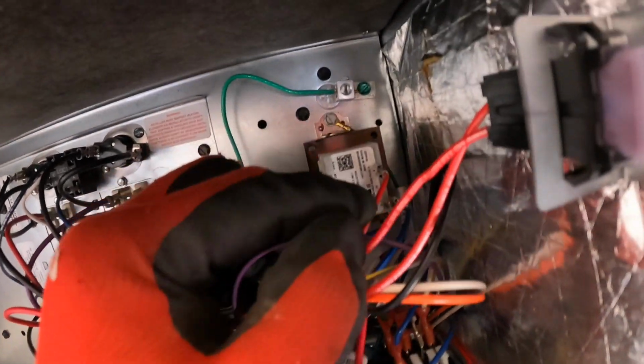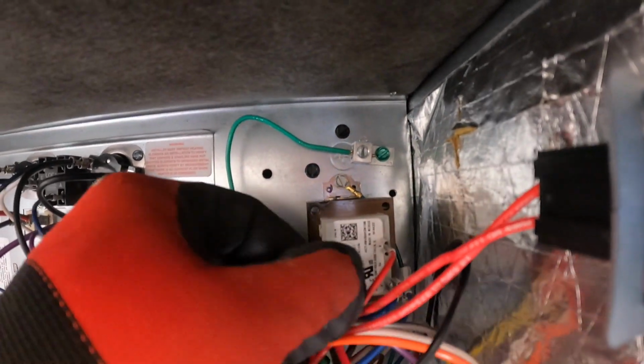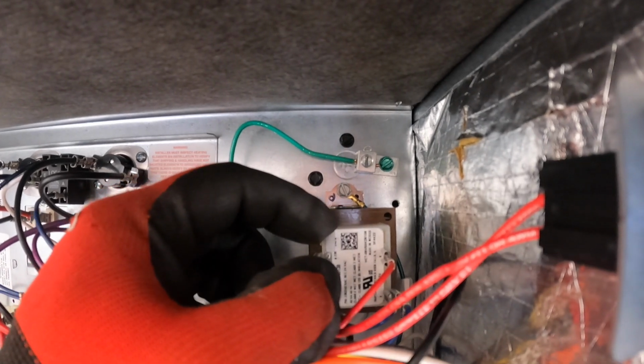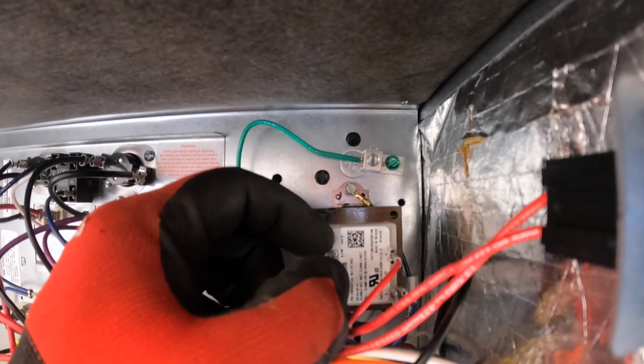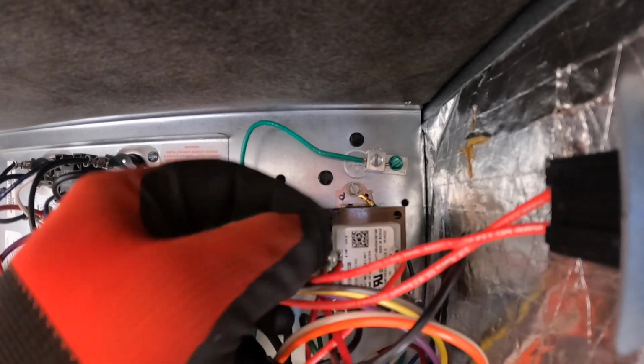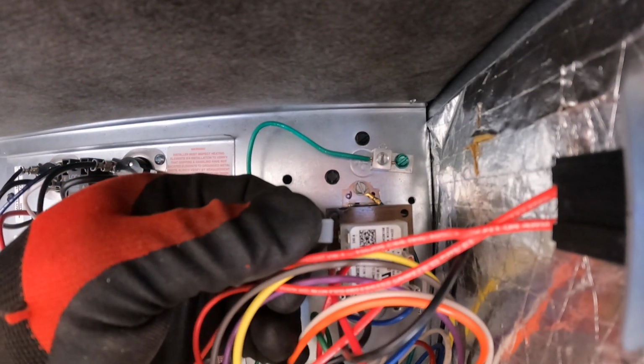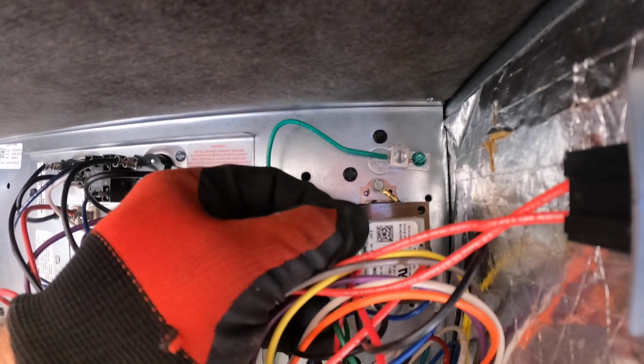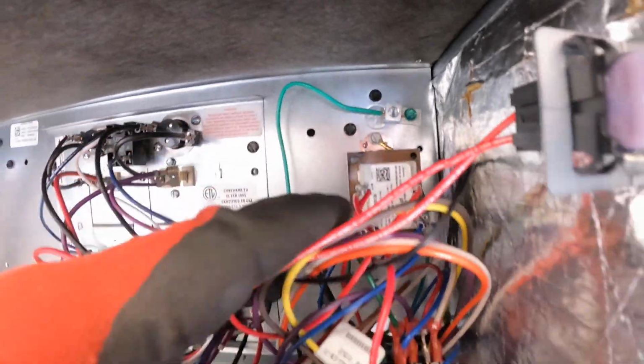While we're at the transformer, I moved my primary tap from the 240 at the top down to the 208, which is one down. It's got this little plastic cap that covers the unused terminal, so I just moved it back up.